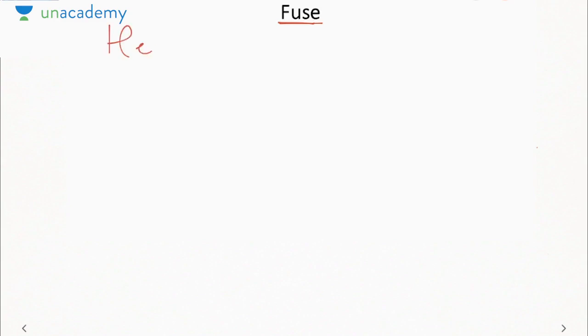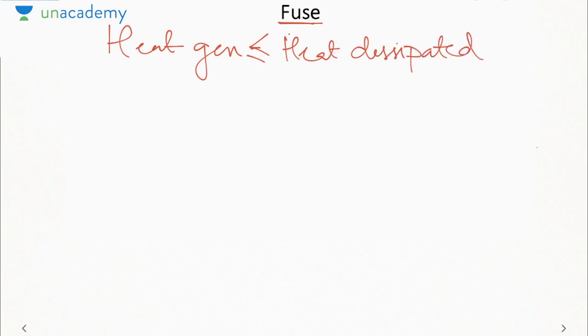Now, if heat generated is less than or equal to heat dissipated, then the temperature will not increase. Okay, sorry, temperature cannot increase. If temperature does not increase, then the fuse cannot melt down. So that means the minimum fusing current depends on the rate at which heat is being dissipated from the system.